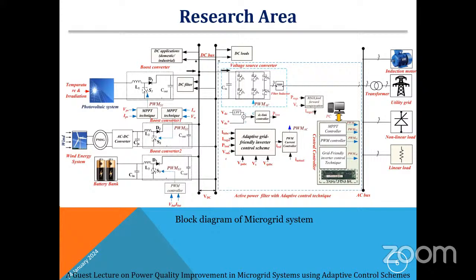After the boost converter, at the DC bus terminals, the DC bus voltage will be maintained constant. If you do not maintain a constant DC bus voltage, we can't send the maximum power from the renewable energy sources to the local loads or utility grid with unity power factor. So the first important control in the microgrid system is DC bus voltage control. And here you can see the battery bank. Why are we using the battery bank? Suppose the power is normal and available from the photovoltaic system, then the power can be delivered directly to the DC bus, and after that, by using a voltage source converter, we can send that power to the local loads. When there is a deficiency of power from the renewable energy sources, at that time the battery bank will supply power to the local loads. That is the reason we are using a battery bank here, for power backup purposes.